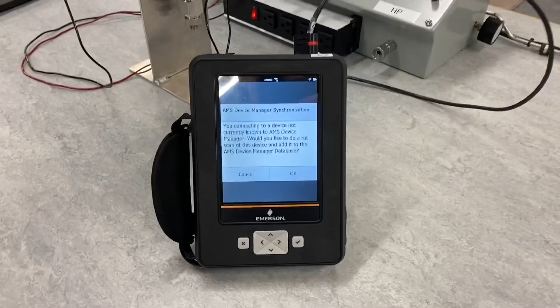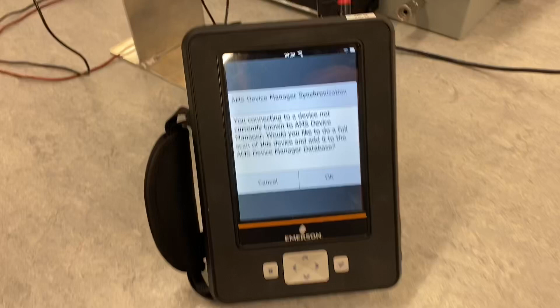Looks like it's going to find it, and then what we'll do is a quick 0 on the device, and we're going to show how that 0 change gets updated in the audit trail of our database over here when we go and reconnect and sync our Trex communicator to it. All right, so this is the first time that the AMS Trex device is actually connected to the transmitter. So we're getting this message saying that the device is not known to the AMS device manager and asking us if we would like to do a full scan. So we'll click OK to that.